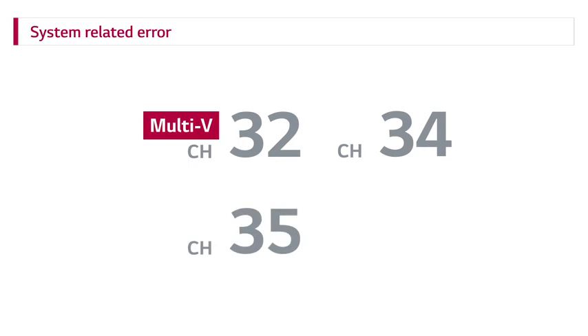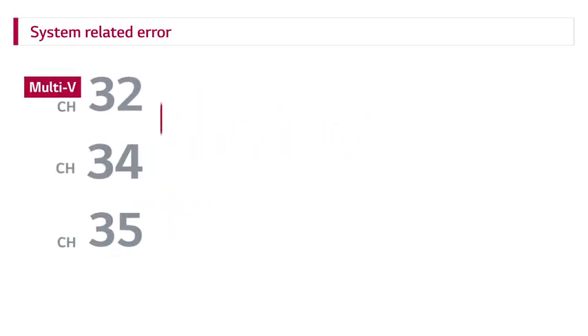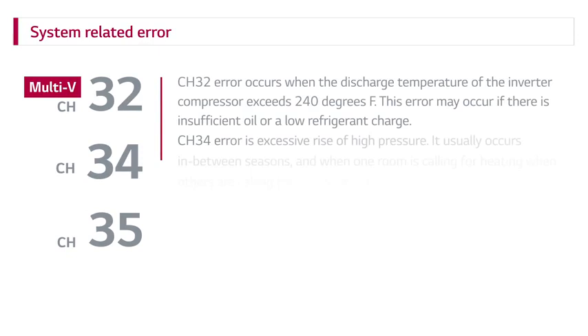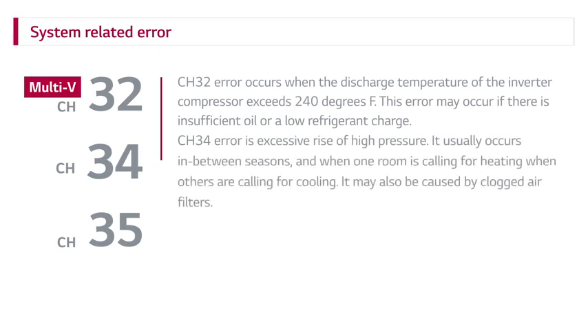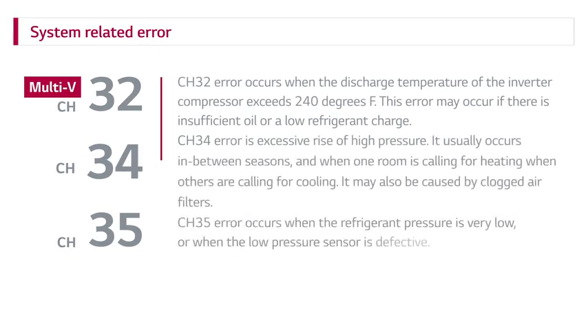CH-32 error occurs when the discharge temperature of the inverter compressor exceeds 240 degrees Fahrenheit. This error may occur if there is insufficient oil in the compressor or possibly a low refrigerant charge.